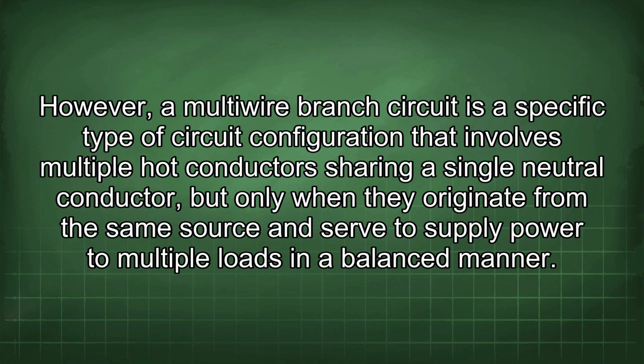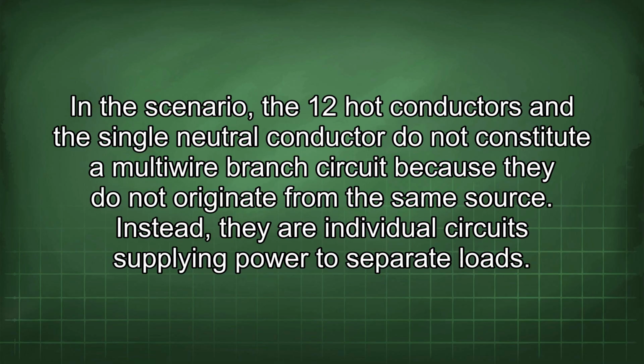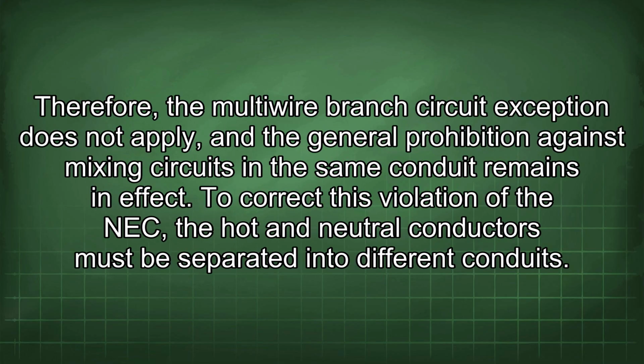In the scenario, the 12 hot conductors and the single neutral conductor do not constitute a multi-wire branch circuit because they do not originate from the same source. Instead, they are individual circuits supplying power to separate loads. Therefore, the multi-wire branch circuit exception does not apply, and the general prohibition against mixing circuits in the same conduit remains in effect.